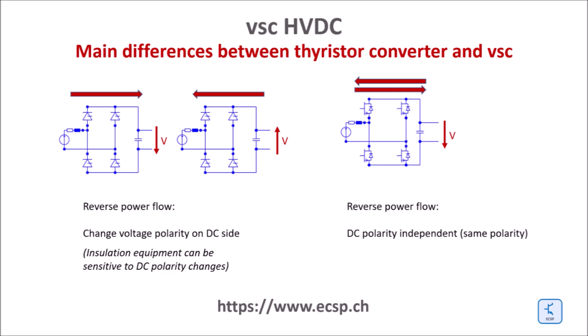Second, the thyristor converter works as a current source; current always has to flow in the same direction. To change the direction of power flow, the polarity of the transmission line on the DC side has to be changed. Some high voltage equipment may be sensitive to these DC polarity changes. VSCs, on the other hand, control the direction of the current on the DC side, so the power flow direction can be controlled without changing the polarity on the DC side.